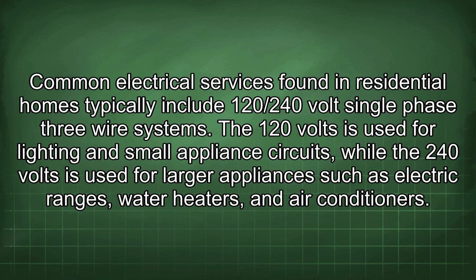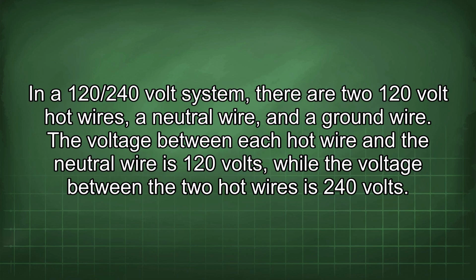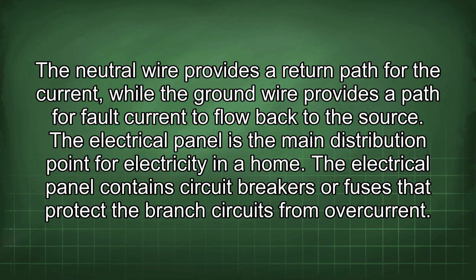Common electrical services found in residential homes typically include 120/240 volt single-phase 3-wire systems. The 120 volts is used for lighting and small appliance circuits, while the 240 volts is used for larger appliances such as electric ranges, water heaters, and air conditioners. In a 120/240 volt system, there are two 120-volt hot wires, a neutral wire and a ground wire. The voltage between each hot wire and the neutral wire is 120 volts, while the voltage between the two hot wires is 240 volts. The neutral wire provides a return path for the current, while the ground wire provides a path for fault current to flow back to the source.